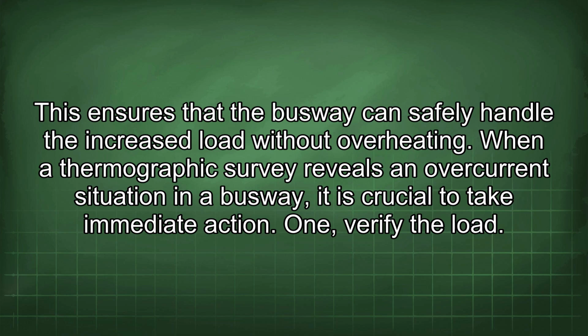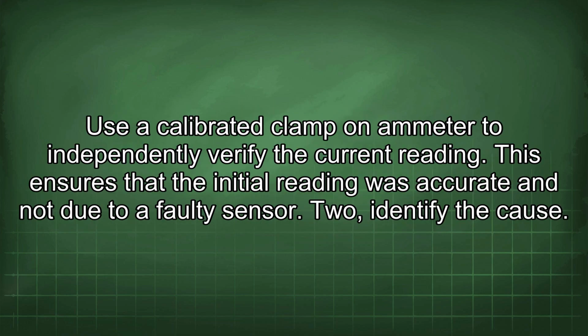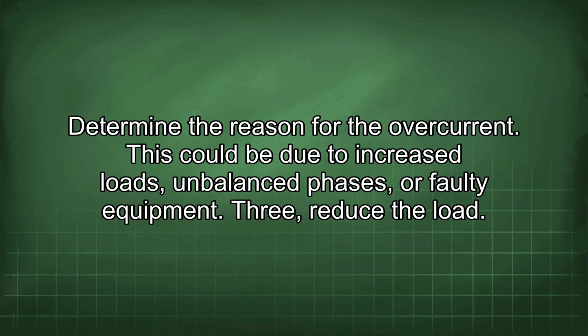When a thermographic survey reveals an overcurrent situation in a busway, it is crucial to take immediate action. 1. Verify the load. Use a calibrated clamp-on ammeter to independently verify the current reading. This ensures that the initial reading was accurate and not due to a faulty sensor. 2. Identify the cause. Determine the reason for the overcurrent. This could be due to increased loads, unbalanced phases, or faulty equipment.